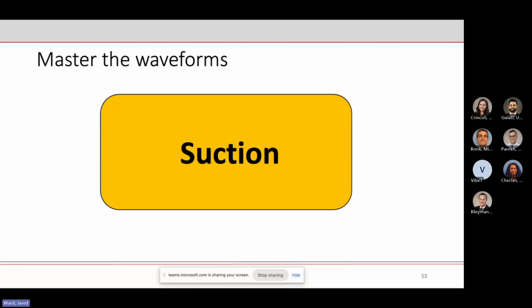And then the last thing we'll go over really quick is suctioning. This is going to be the bane of your existence with these devices. So basically, a suction alarm pops up on the Impella. And what you've got to do is, A, you just reduce the P level. So if you're on P8 and you're starting to get suction events, maybe it's just running a little bit too high, and you can drop it down to like P7 or even P6, and the Impella will just start cruising along again. But then you've got to go hunting for why it happened in the first place.